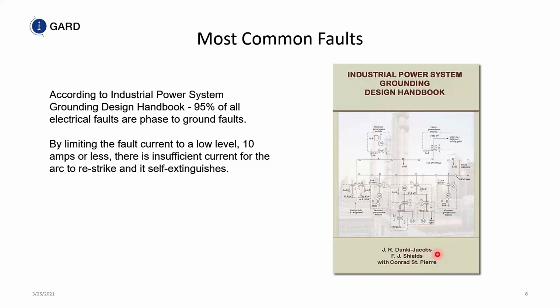Now remember, it takes time to eliminate the single phase to ground fault if you have the maximum amount of fault current. If you don't have the maximum amount of fault current and have the minimum amount of fault current, you may not necessarily trip at all.